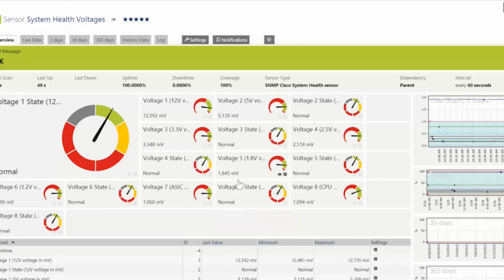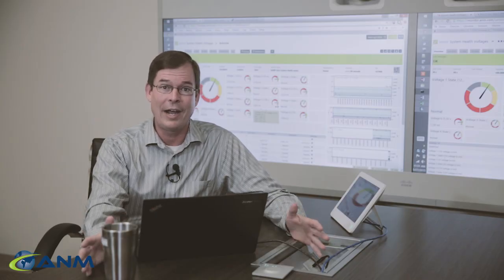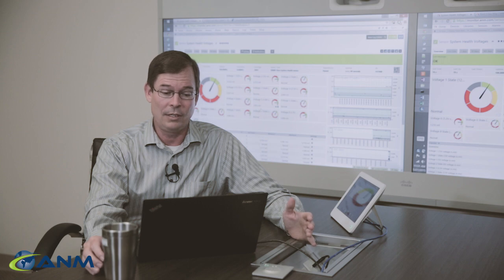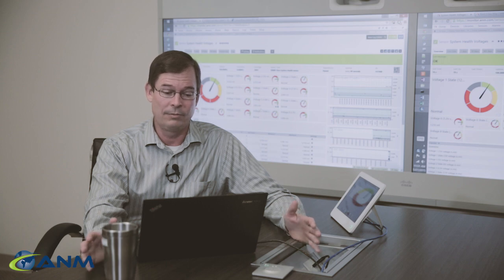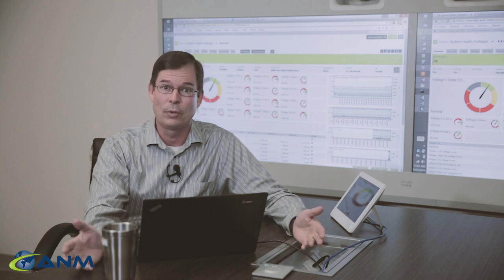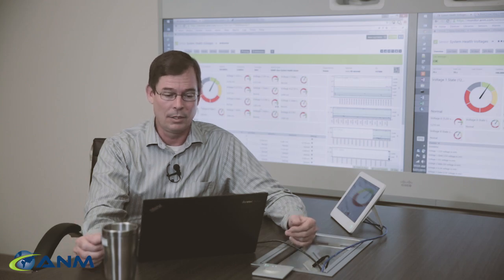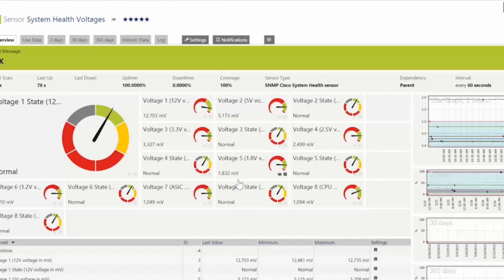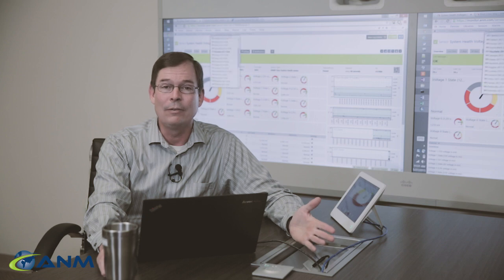So we're very granular and we're really drilling down in deep to make sure that we're as we said proactive and we're staying atop of these issues and resolving them before the customer may even know they happen. If the temperature starts spiking and it gets above the warning threshold we'll get a ticket. We'll either contact the customer or actually travel to the site depending on our agreement with that customer to figure out what's going on before it gets into the red zone and becomes a real problem and damages the equipment. That's a prime example of what we mean when we talk about our proactive monitoring and systems.